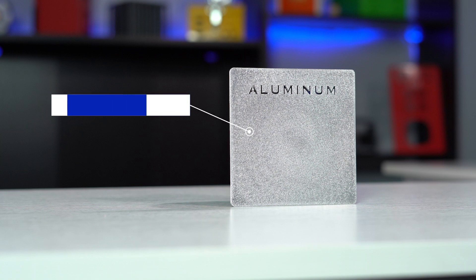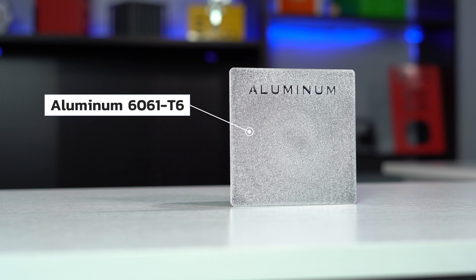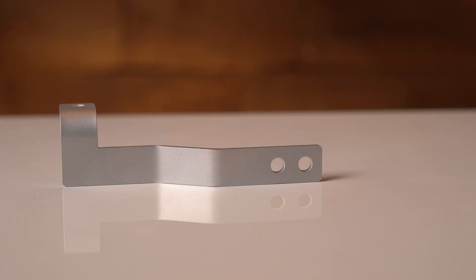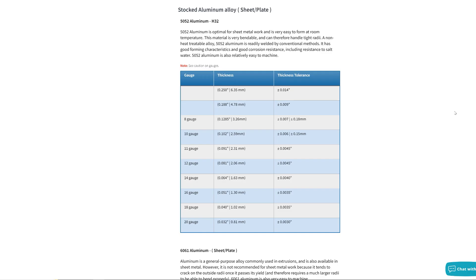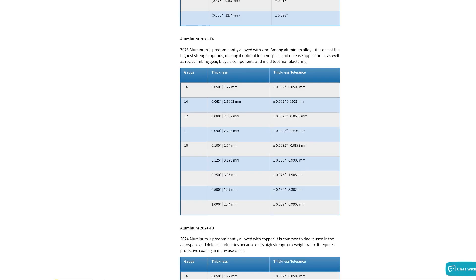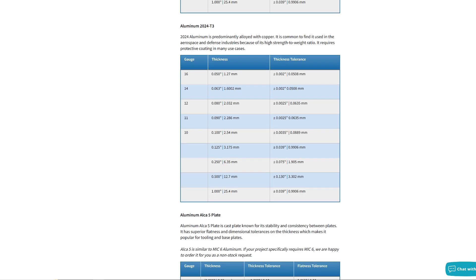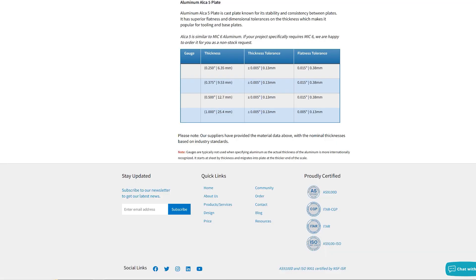On the other hand, while we stock many different aluminum alloys, 6061-T6 is generally considered a favorable alloy to build bus bars. This is because it has a favorable combination of mechanical strength, corrosion resistance, conductivity, machinability, weldability, and cost. The other alloys we stock include 5052-H32, 7075-T6, 2024-T3, and aluminum Alca5.